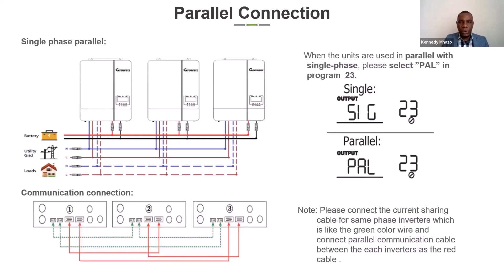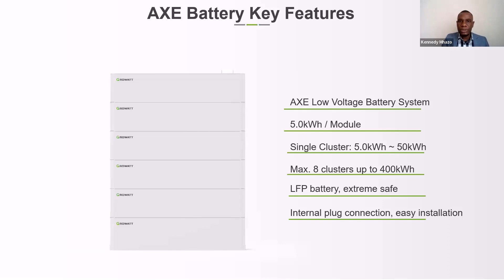One of our energy storage lithium batteries is the AXE, which is a low voltage battery. This one has a capacity of 5.0 kilowatt hours per module, but you can put them in a cluster which goes up to a maximum of 8, which is 400 kilowatt hours. And it's very easy, plug and play, no need for cables. It's just a direct connection from one module to the next module. Then you just have two outputs, positive and negative, straight from the top module going to your inverter input, of course via your DC breakers and your protection system.